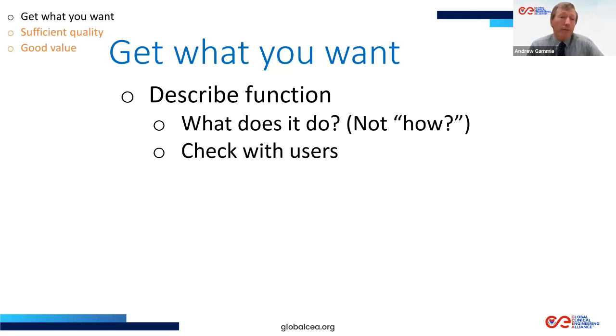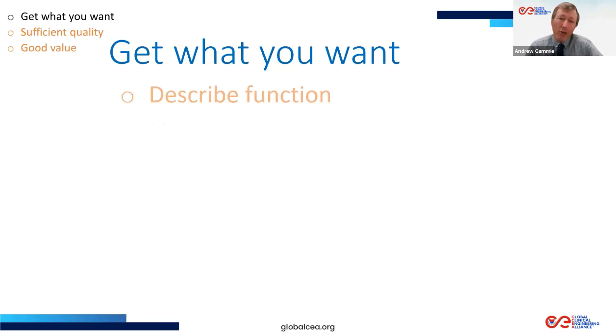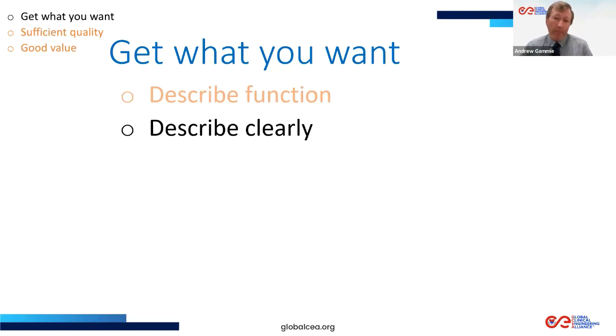I've seen a specification that asks for a knife. Well, if you get a surgical knife or a Bowie knife, you're going to get two very different devices. Make sure you know which one it is. So describe the function and make sure that you know what you're asking for. When you're doing that, describe it clearly. So don't call it a sucker, call it a suction machine. Or if you're using a standard system, you call it an aspirator. And then you say where it will be used. Use those standard names, which is aspirator in fact, but suction machine is normally okay as well. Sucker is not a standard name. So you could get all sorts of devices if you just use that.